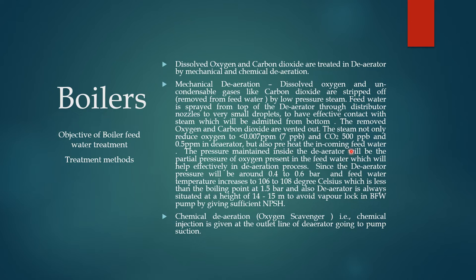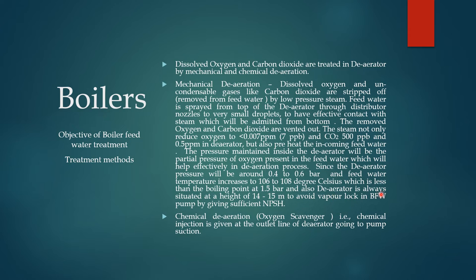The steam also preheats the incoming feed water to around 106 to 108 degrees centigrade. The pressure maintained inside the deaerator is the partial pressure of oxygen present in the feed water, which helps effectively in the deaeration process. The deaerator pressure is around 0.4 to 0.6 bar, and the feed water temperature is increased to 106 to 108 degrees centigrade, which is less than the boiling point at 1.5 bar.